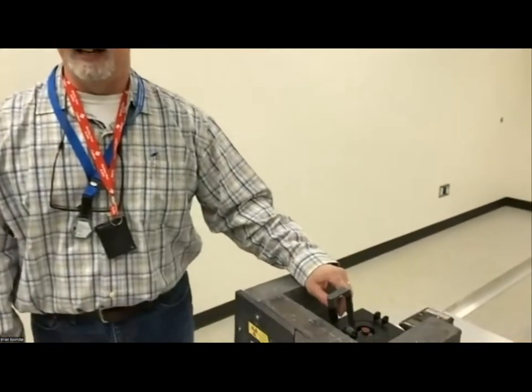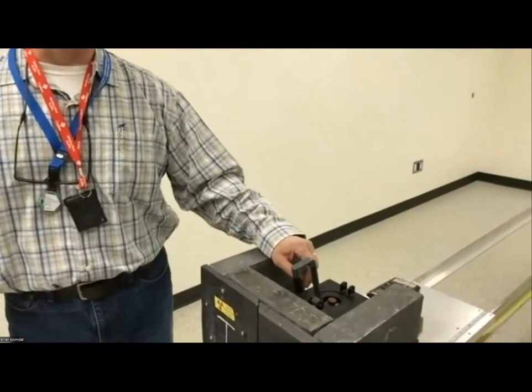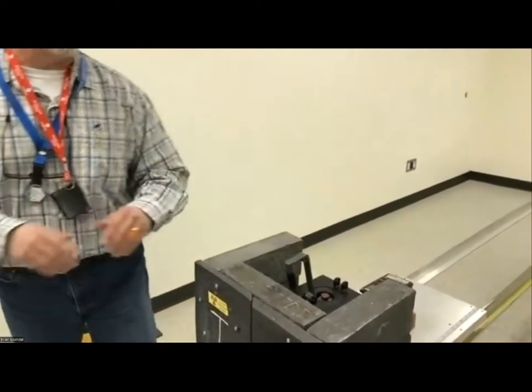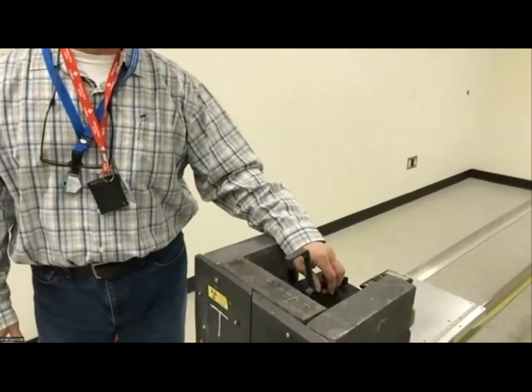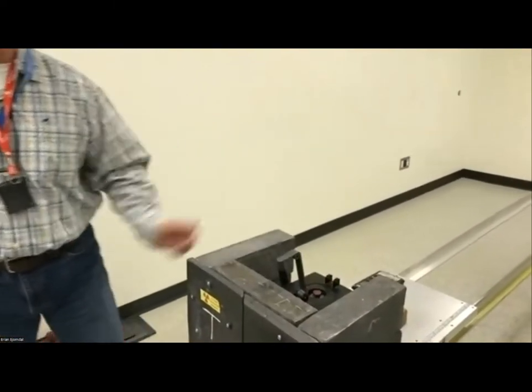But there are devices out there which have pneumatic controls where you can stand back, open up the shutter, and let it go. But for this particular device, it is manual. So we're doing a long exposure, which Tammy sometimes has to do for TLDs, because we also use it for our TLD type of work. He might have to sit here for 8 or 10 or 15 minutes and expose the instrument. So it's not ideal for that, but it can be used for that. But generally, we're talking a minute or so at a time, and then you drop it, and then you would reset it.